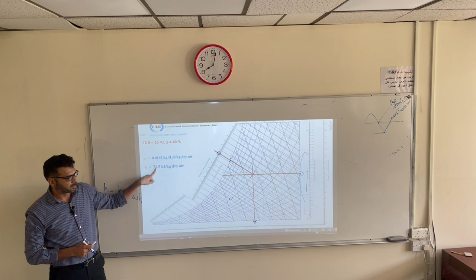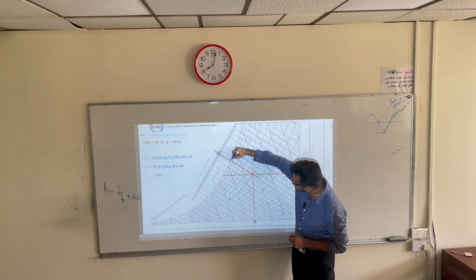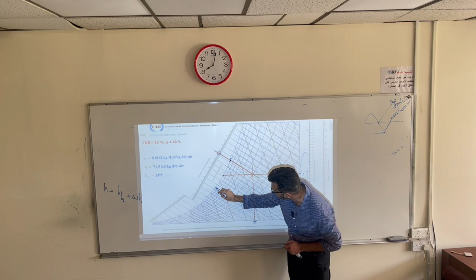Okay, so now enthalpy is done, specific humidity is done. Next is dew point and wet bulb temperature. Same line, but wet bulb values are written here. These are enthalpies, so wet bulb values are written here. This is 20, this is 25, so you will say 21, 22, 23, 24 almost. These are wet bulb temperature lines. Next, dew point, same horizontal. Here you read specific humidity, but here this will be dew point. So this is wet bulb, and this is dew point. Same scale, but now it is 15, 16, 17, 18, almost 19 point something. 19.4. So it's easier than using those equations.